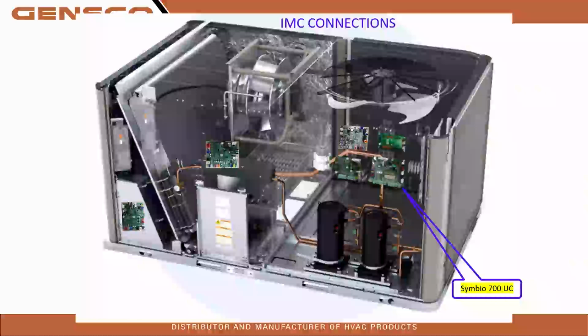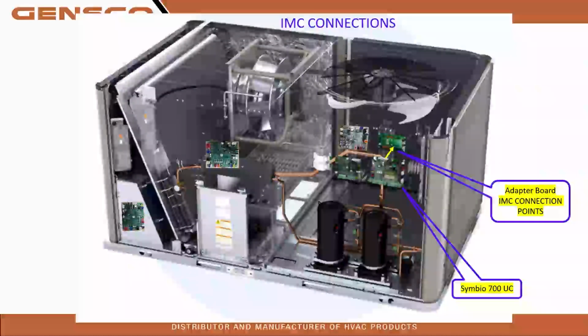IMC connections. Here's our Symbio 700 board. Again, this is a great slide I can send out if you need it. This just shows you the path of your IMC connection points. This shows that it's passing through a hinge right here, and there are hinge Molex plugs right here. Now, some of those can come disconnected during transport. That's why I wanted to show you this. If we have an alert that our adapter board's not communicating, this is the wire path that we're going to follow to check connections.